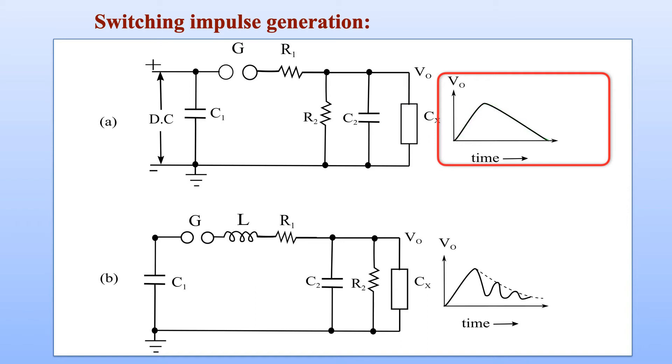Let us now focus on the lower circuit which consists of a series inductor L inserted just ahead of resistance R1. Many times we are interested in generating switching impulse voltages which are damped oscillatory in nature. In that case, a series inductor is added and the effect is visible in the highlighted region of the diagram. You can see that oscillations will be present in the output voltage. Although oscillations are present, this will still be unidirectional voltage.